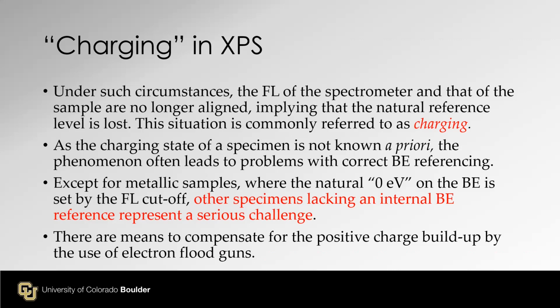In SEM imaging, charging is annoying, but we are not measuring the energy of secondary electrons. So it's annoying, but it's okay, and we can put a coating if necessary. It doesn't work for XPS or any surface analysis instrumentation, and the charging state of the sample is basically unknown. So we have to do something.